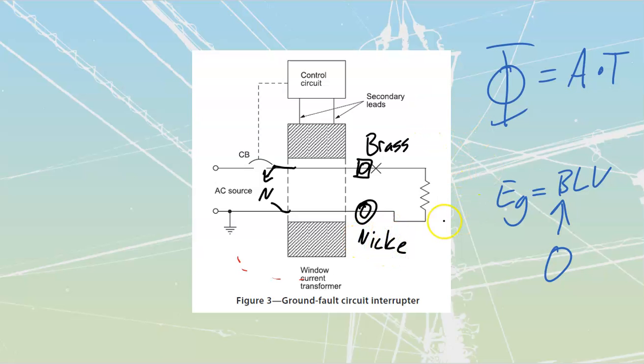And that's why when we connect up a GFCI breaker, or anything that's downstream of a GFCI, that we need to have... Get out of there, Eli. Come on, move. Sorry, Eli's just mangling. That's why when we make these connections, we have to connect our neutrals from our circuit to the actual device. So it goes through the device. All the rest of this is just buried inside of that circuit breaker. We don't need to worry about that.